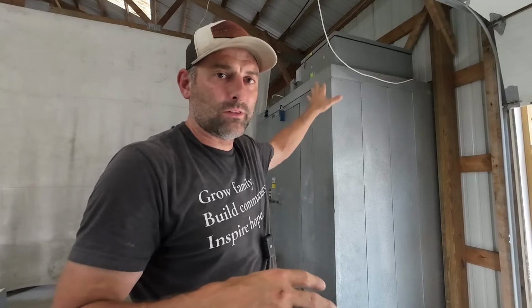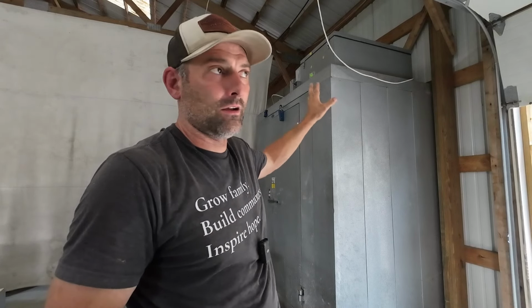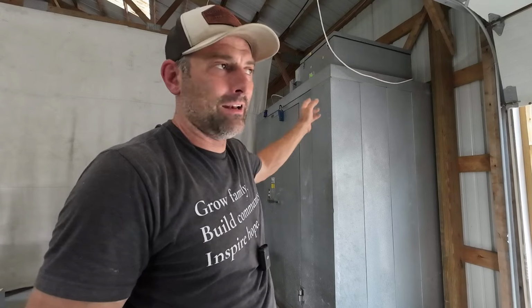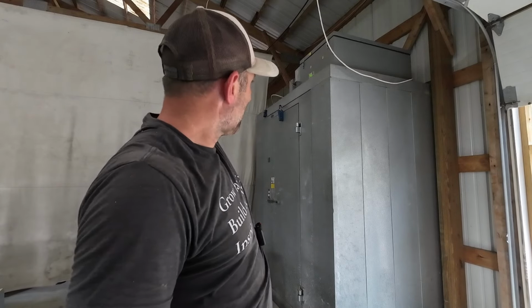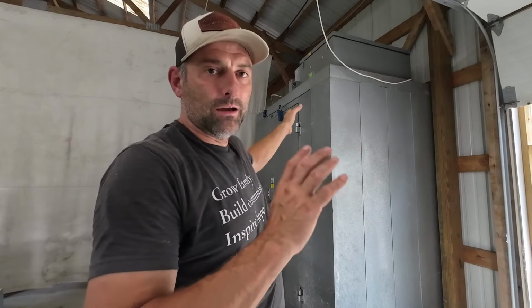It took us a little longer to install since it's our first time, and we had to set up our own electrical in there. We took electric that was run over here to test the old ancient cooling unit when we first got it, rerouted that, put it through a hole, protected it in place, and mounted it to the wall. So the lights are working inside now, and so is the actual AC unit with the Coolbot system.